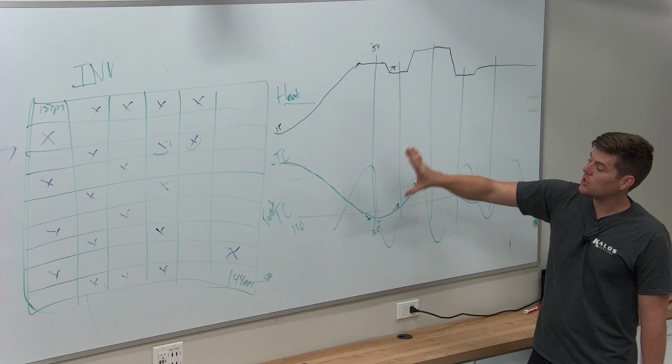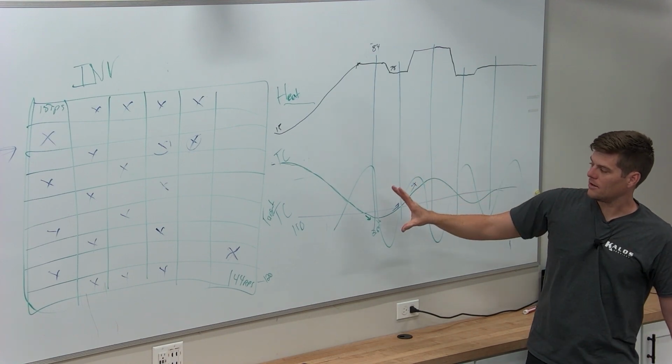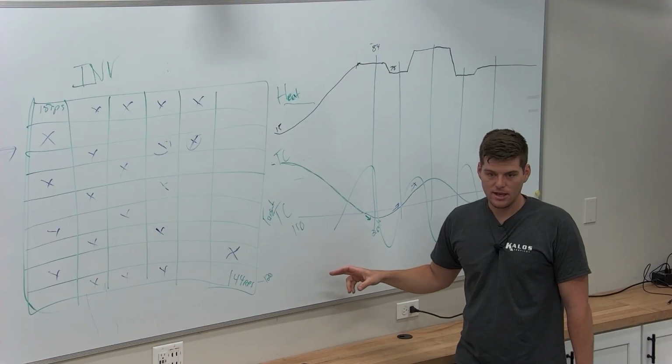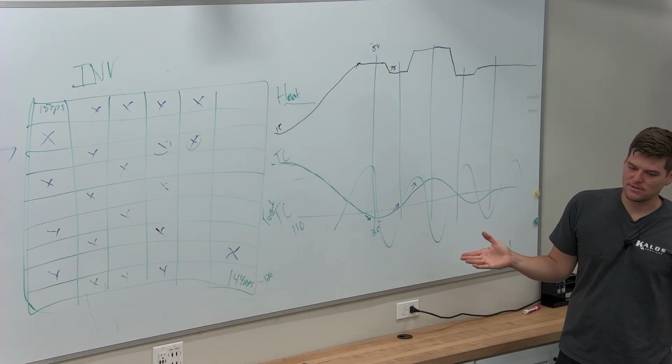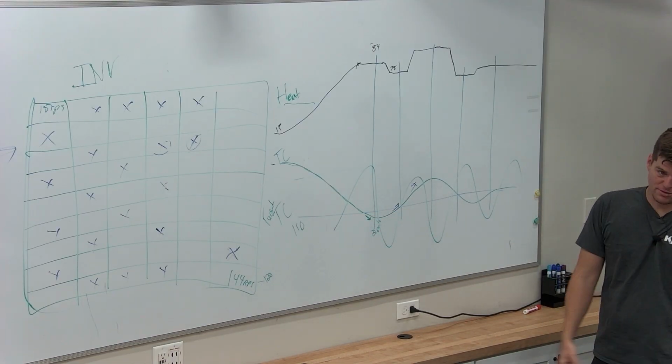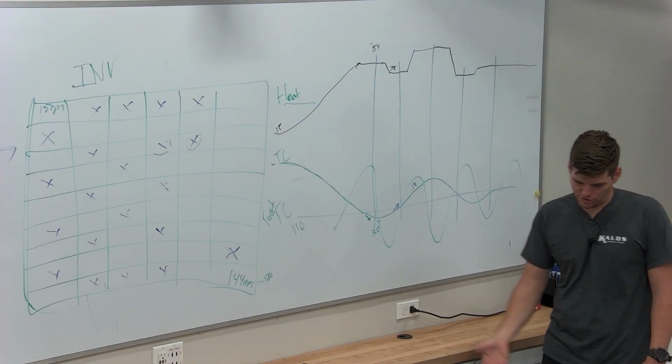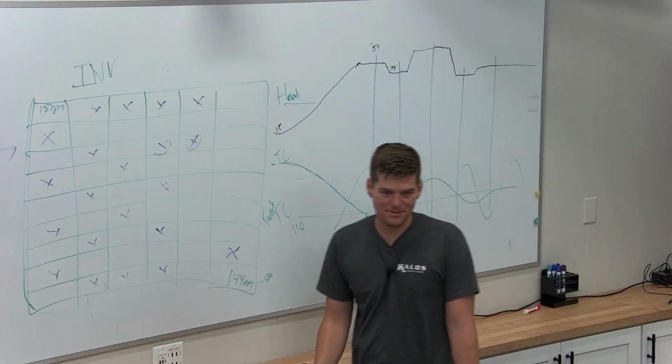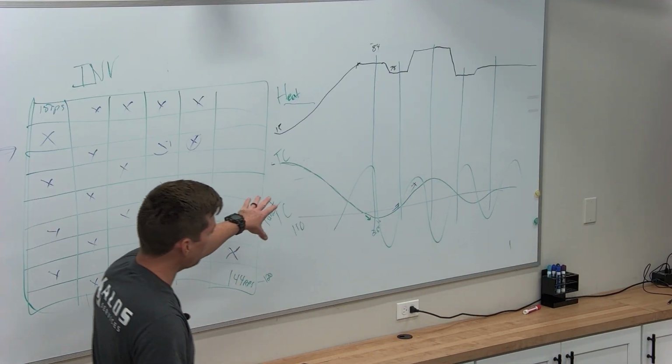But again, these are all things that we can measure and look at. Am I hitting targets? And when I hit targets, what happens? If it maintains targets, but all my valve pulses are open and my superheats suck, they're 30 degrees, there's a problem. Hitting targets isn't the end-all be-all, but it is the basic mode of control.